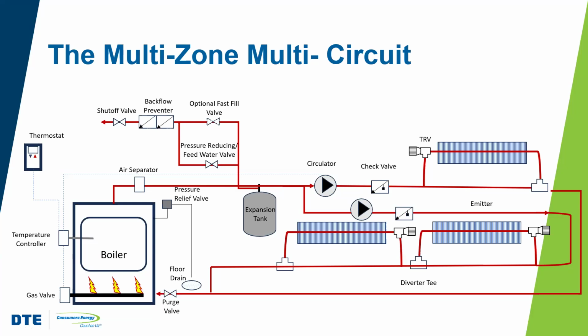It's not necessarily a con, but something to think about here. You've got to have a check valve in each branch so that there's no flow when a circuit is not in use. And you may still have, in a particular branch, this branch has just one emitter, but this one here has two, right? And so in that particular branch, you still may have water flowing from one emitter to another emitter, so that second emitter will not have the same incoming temperature as the first emitter. So again, you've got to make sure that the emitters are sized for their location in the system.